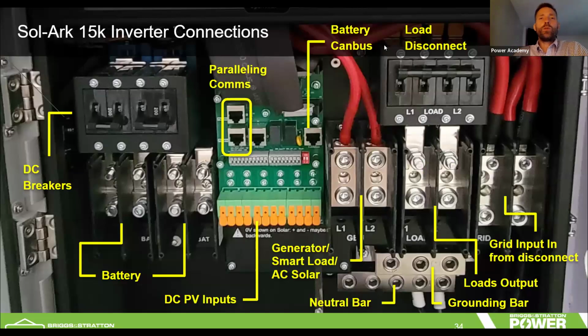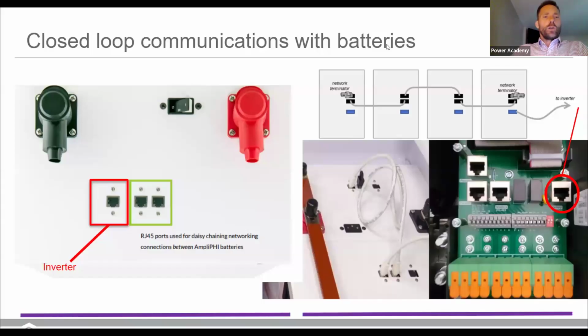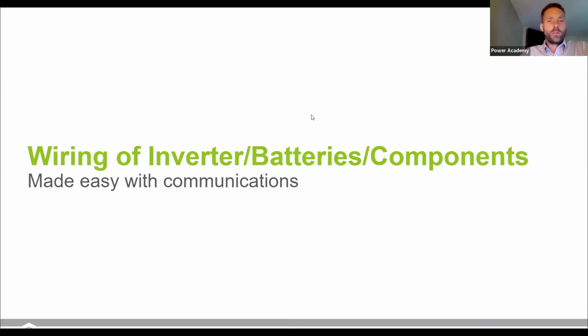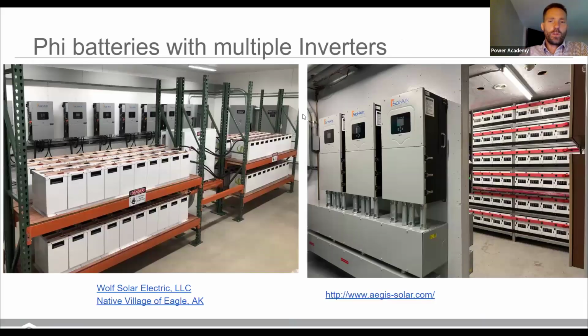Keep in mind, when you're doing paralleled inverters, you only want to have one bank, right? So you've got to parallel your battery banks and then split out of that combiner to power each of your individual inverters. You would never connect one bank to one inverter and a second bank to a different inverter. We don't do that.